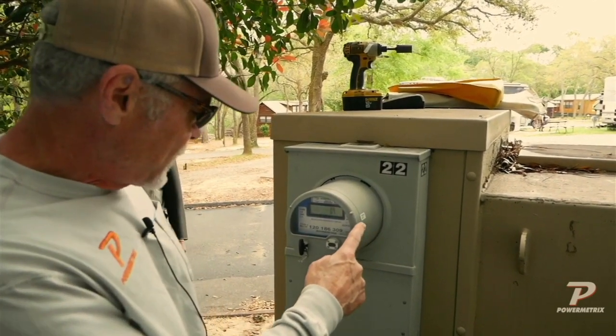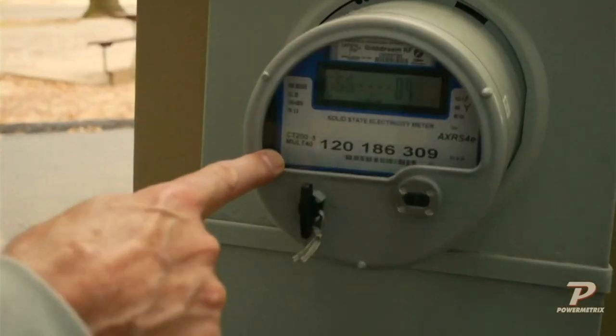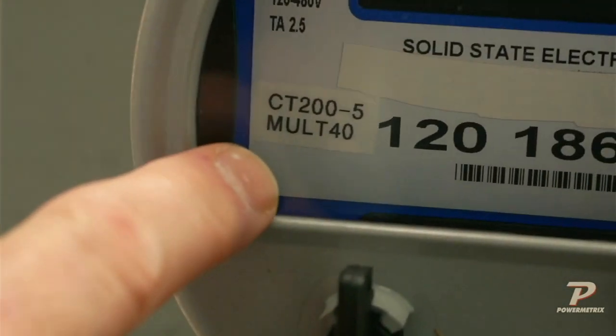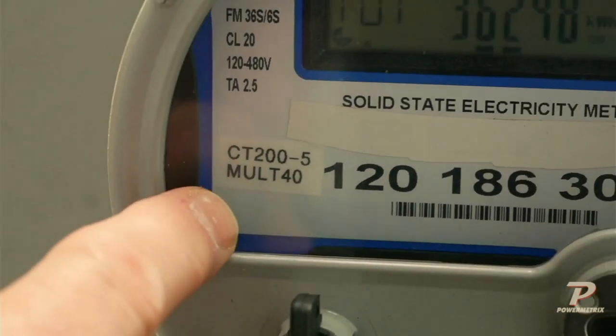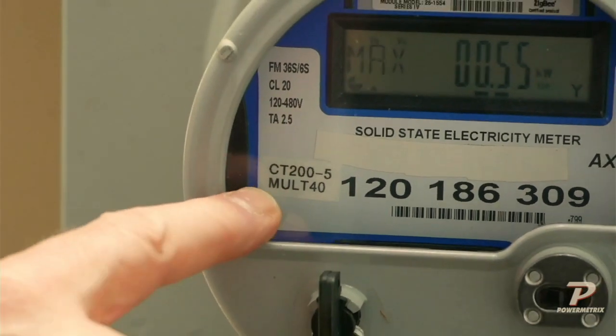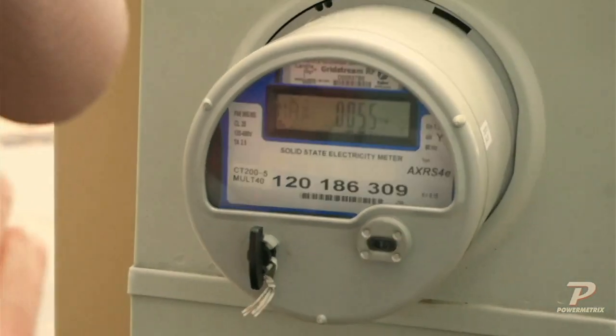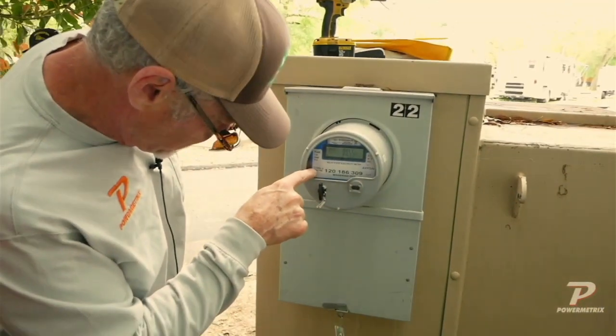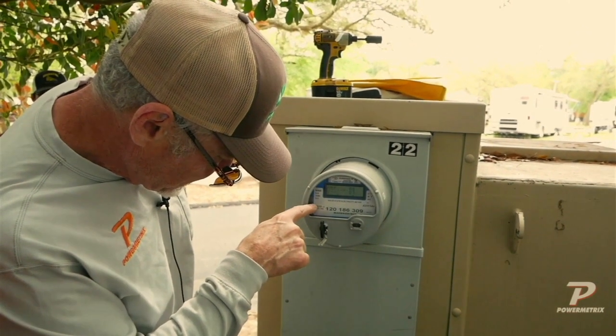You'll also notice, if you can see it in there—I know JP's good with the camera—you can put the multiplier in there too. If the multiplier says 40, which is what it says here, multiplier 40, you can see that the CT is 200 to 5.